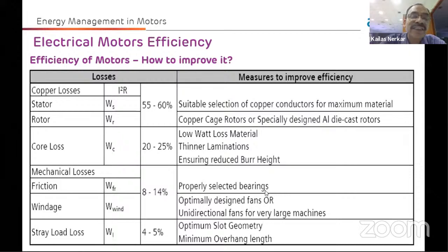Normally what happens is, the motor comes with a fan sent by the OEM. Once that fan gets damaged, people just install any replacement fan, which reduces the efficiency of the motor. The fan installed at the time of repair or maintenance should be as per the optimal design required.